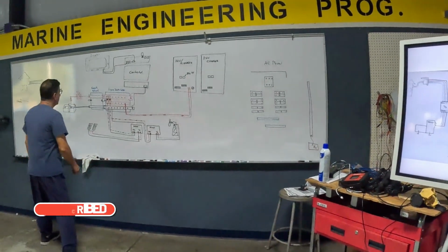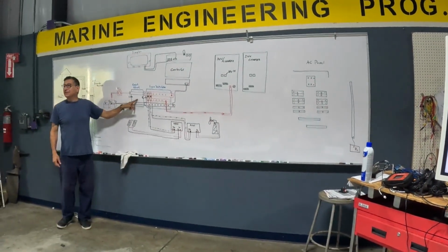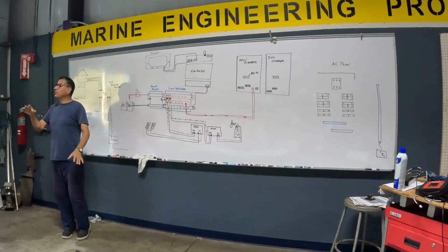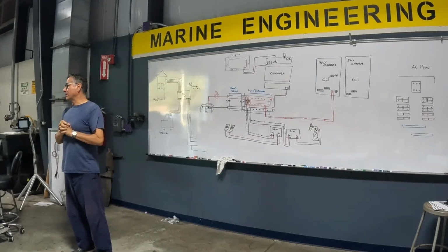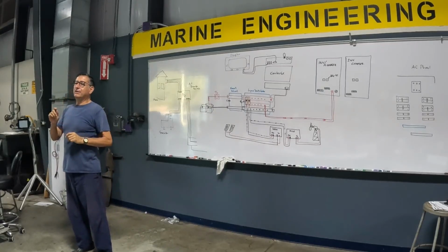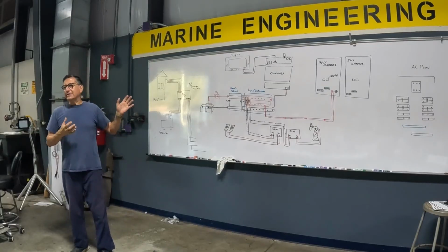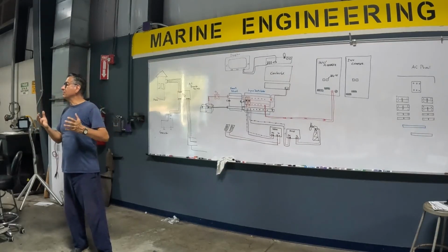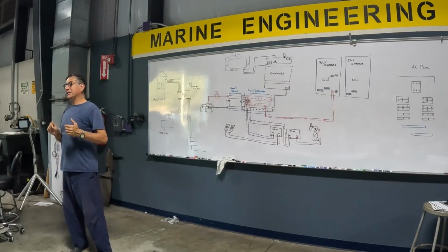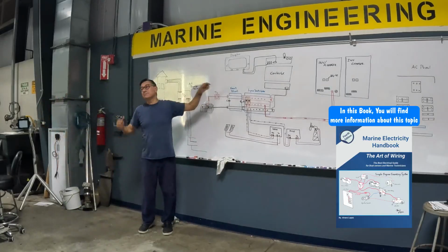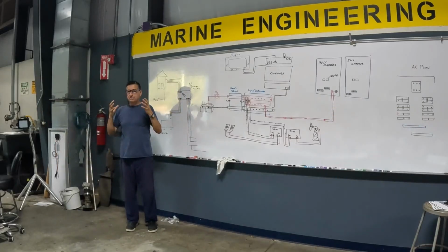The second one is the shunt. This is an intelligent shunt. You remember we used the shunt in DC to protect the ammeter and to read amps. This one is the same. This is used to read how many amps are flowing in the system. But additionally, that element provides information about the temperature of the battery bank and the total power on the battery bank. It is more intelligent. This is why the name is smart shunt. It's a shunt, but it's more intelligent.